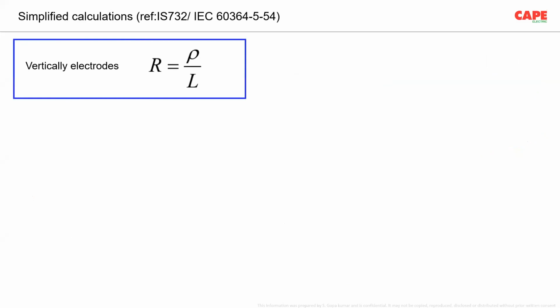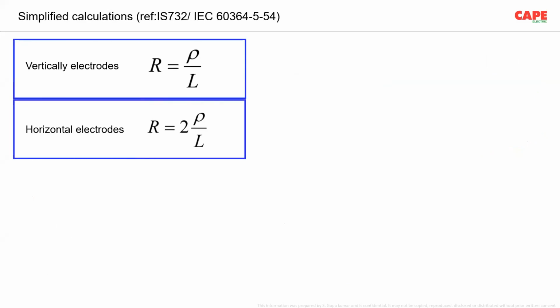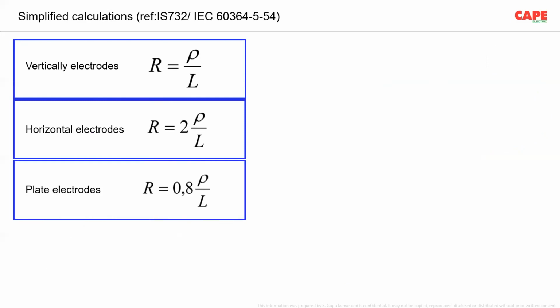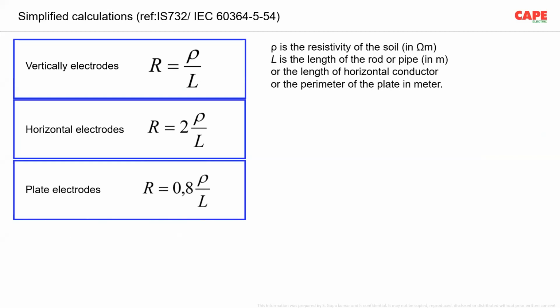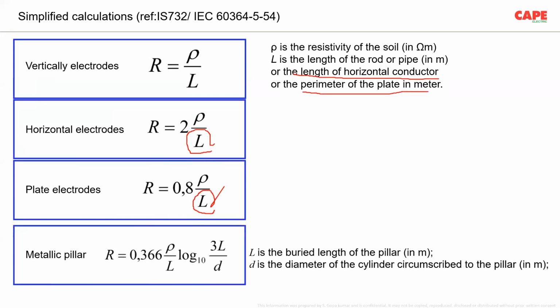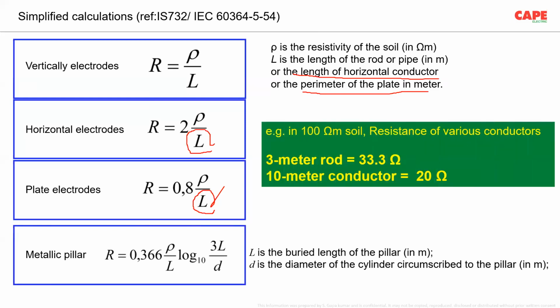Now, how to calculate the earth electrode resistance? In IS 3043, a lot of complicated formulas are there. But nowadays, these formulas are being simplified. IS 732 has very simplified formulas like this: R equals rho by L. You know very well that rho is the resistivity of the soil in ohm meter. L is the length of a pipe or a vertical conductor. In the second case, L is the length of a horizontal conductor, and in the third case, it is the perimeter of the plate in meters. The fourth case, if you have a buried metal pipe or a structural part, then you can also find out the earth electrode resistance. A simple calculation.